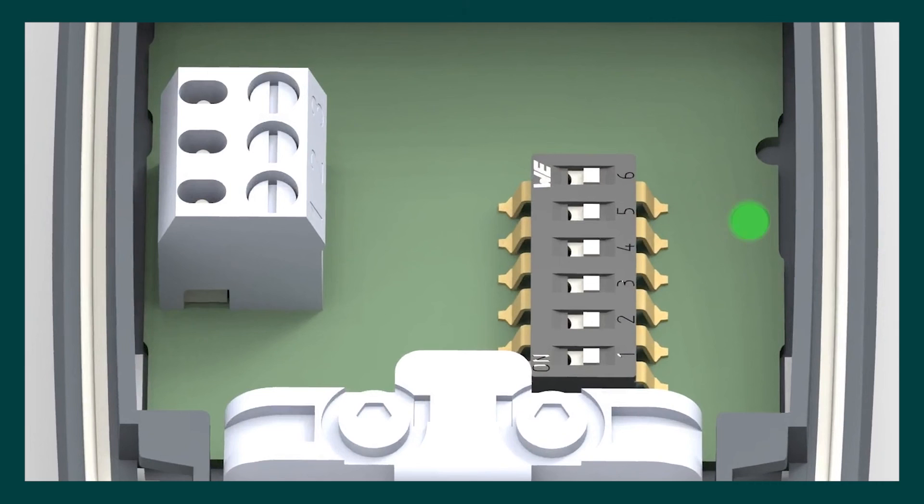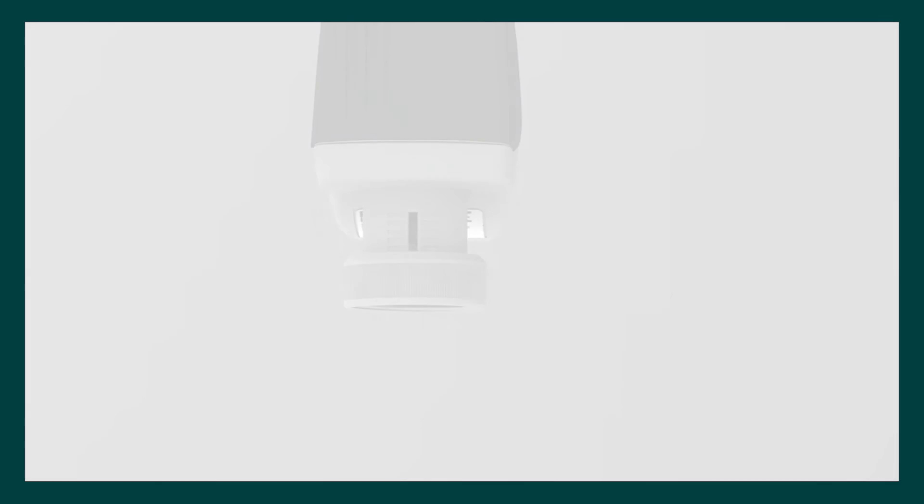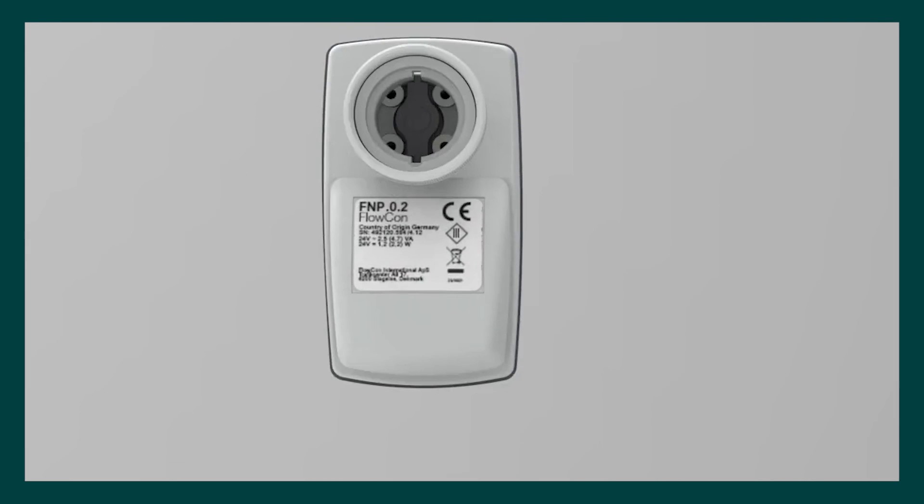Dipswitch 6 should be reset to the off position and should remain in this position whilst the actuator is not fitted to the PICV. Only remount the actuator onto the PICV in the fully open position. Once remounted, turn the power on.